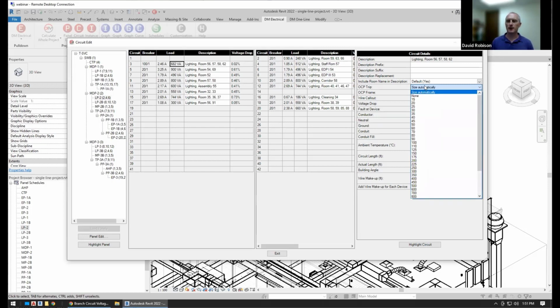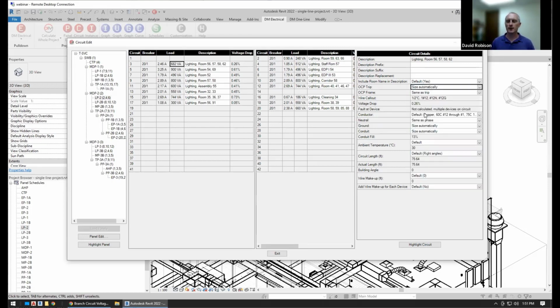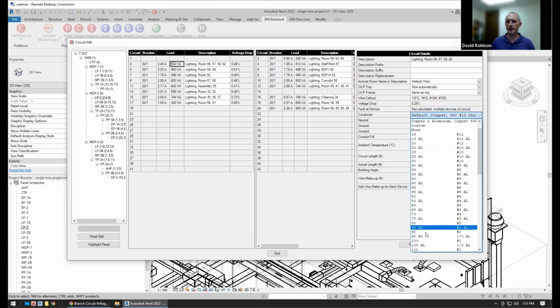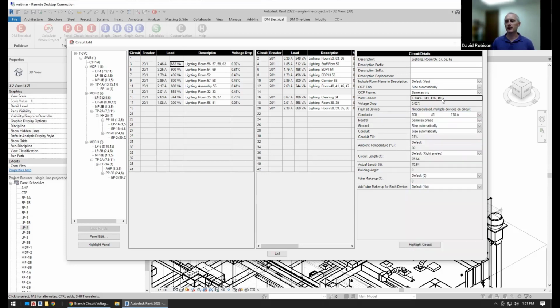If we have our default 20-amp breaker, but we need a very big wire, say we go up to number 1 wire, we actually are going to upsize the ground proportionally at that point. So we end up with a number 1 ground, which is a very large ground, but that's what the NEC requires in that case. So the ground sizing varies a little bit depending on whether you're upsizing your breaker or upsizing your conductors.